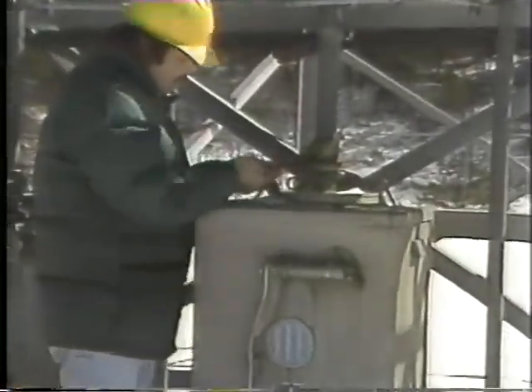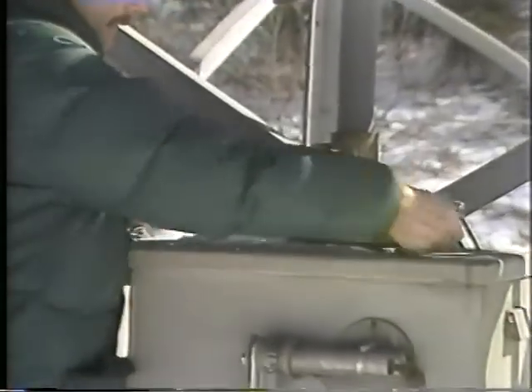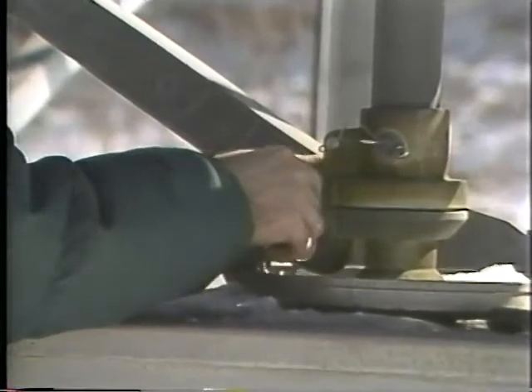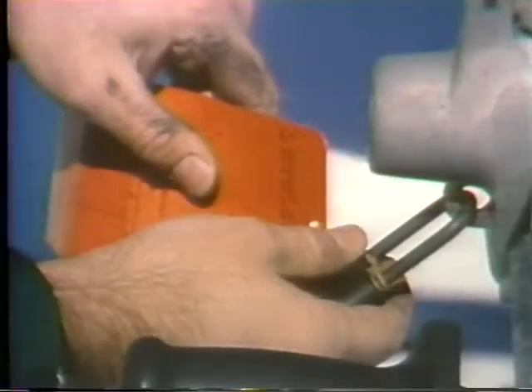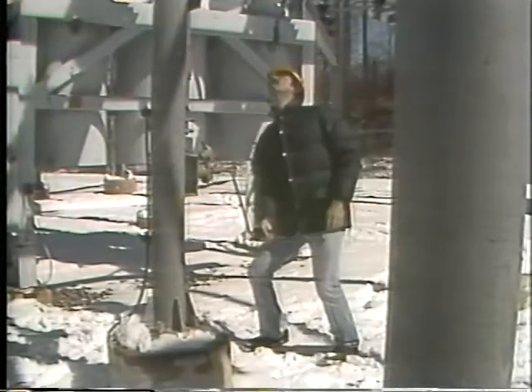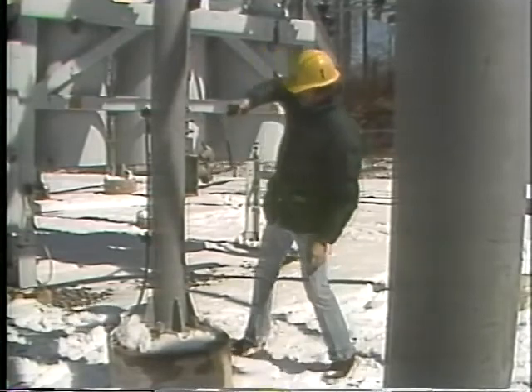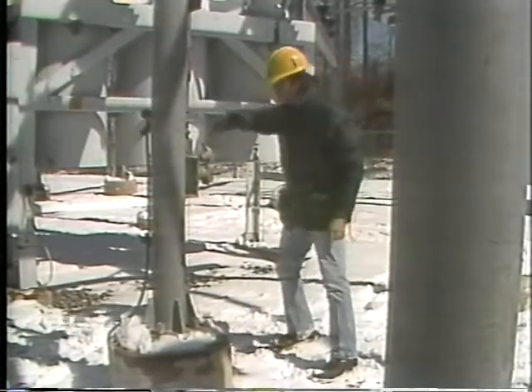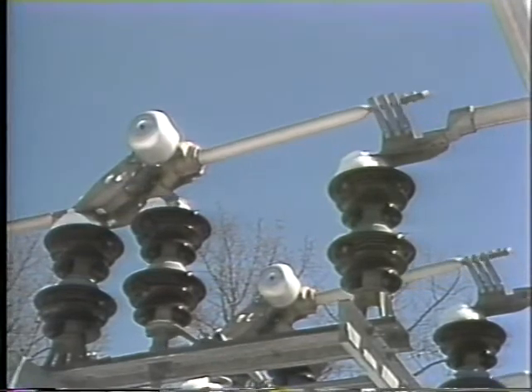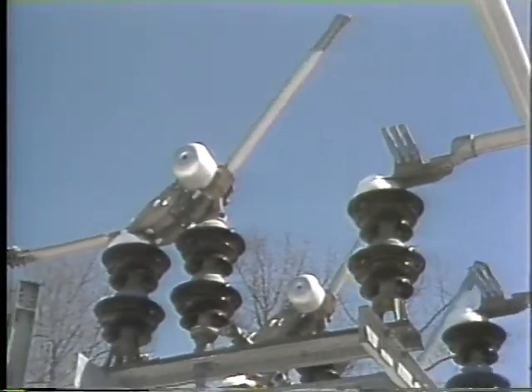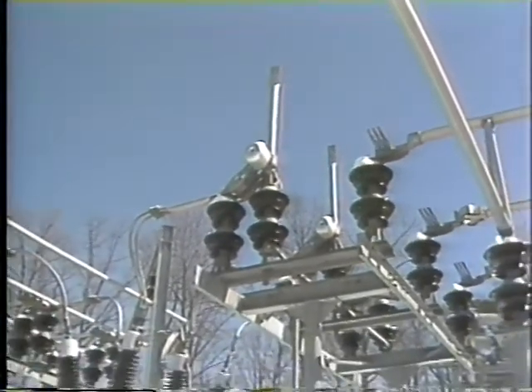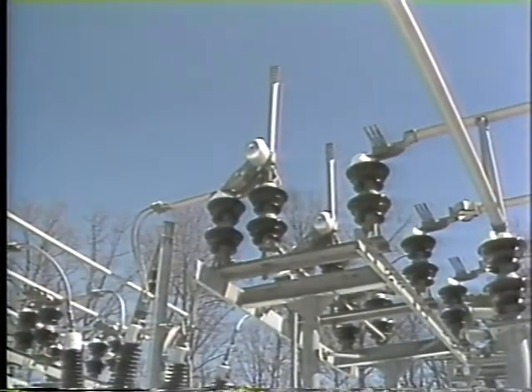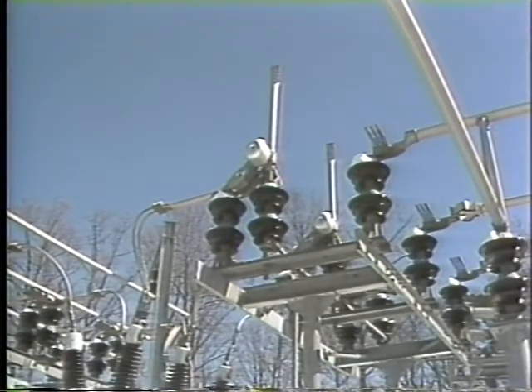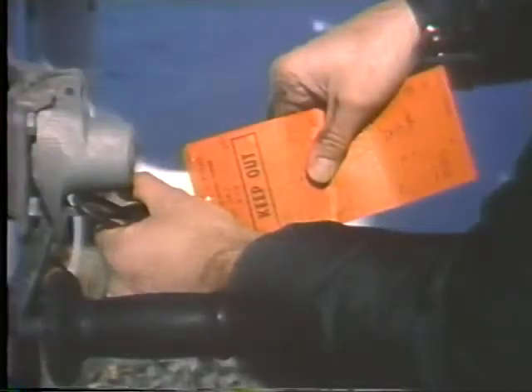It's up to the electrician to lock the motor-operated switch in the open position and tag it out so the transformer primary won't accidentally be energized. His next move is to isolate the secondary. This disconnect is manually operated. Opening the secondary side of the transformer ensures that voltage from interconnected equipment downstream can't feed back into the transformer. Now the transformer is electrically isolated on both sides. This switch is also locked and tagged so it can't be closed accidentally.